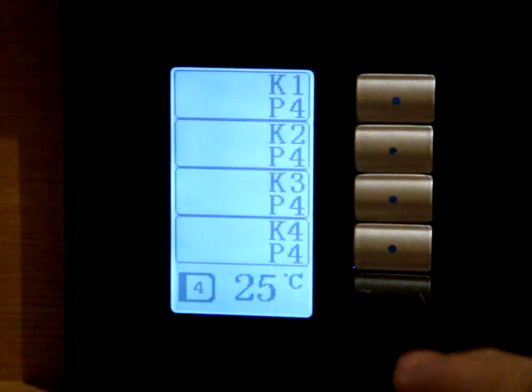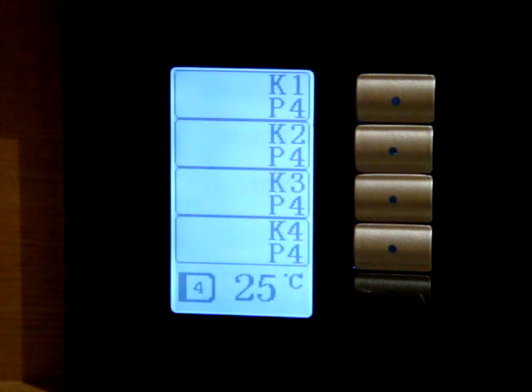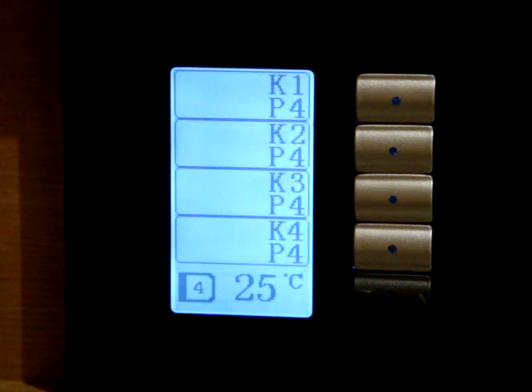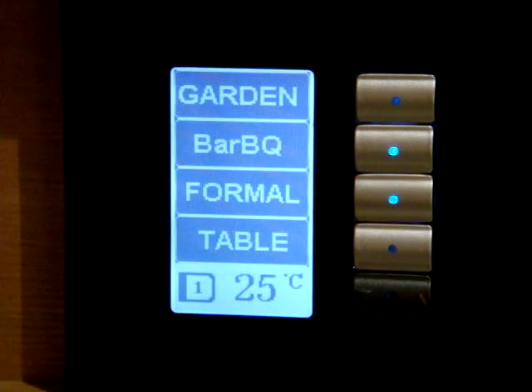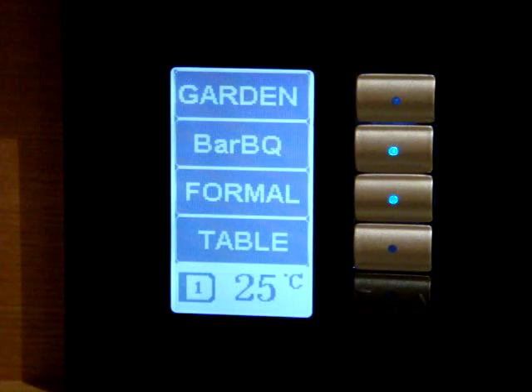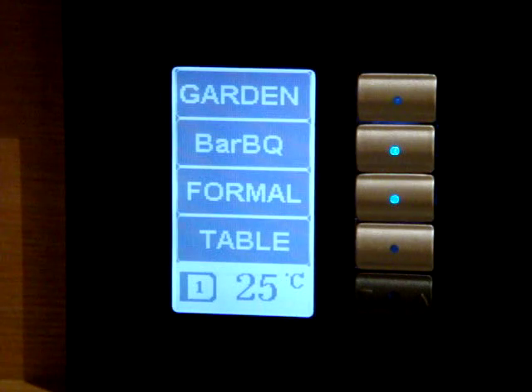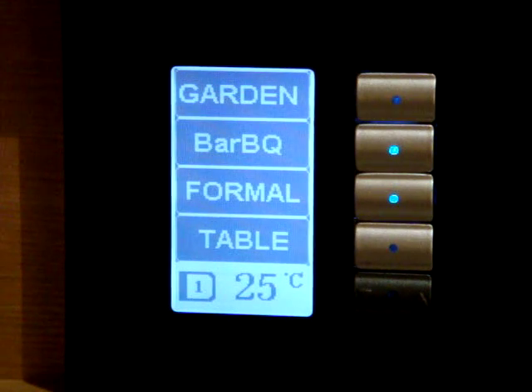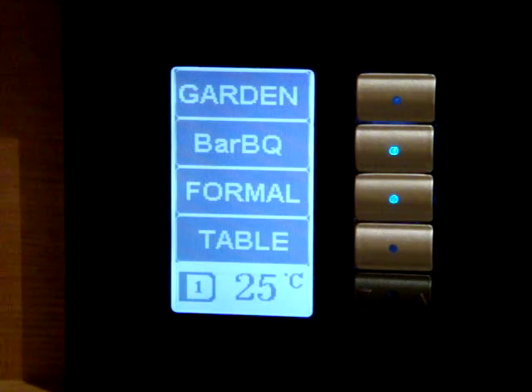It also has a thermocouple to read the temperature and send it to our air conditioning hidden module near the air conditioning unit. This system can control both VAV systems as well as air handling and fan coil units. We can also connect this module to infrared transmitters and control split ACs that need infrared control — we can control the fan speed, the temperature, the heating, the cooling, and we can control through this one systems that use LonWorks or M-net.